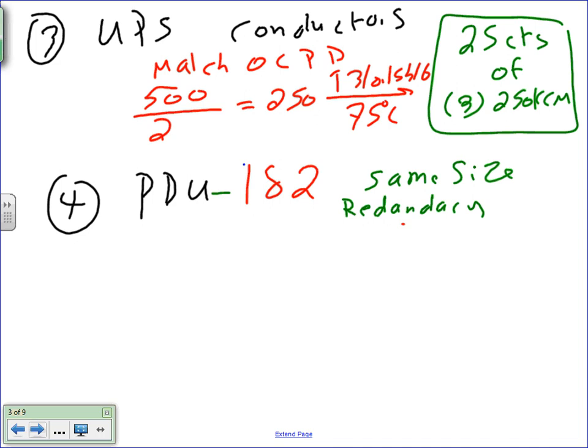Okay, now PDU 1 and 2. I said same size, guys, as the UPS. The same way we size it. I'm not going to repeat the steps. Same way like the UPS, so you're going to get the same calculation, same sizing. Everything is the same, and we have two of them for redundancy. So we're going to size them 100%. Both of them are going to be the same size for redundancy. Remember how if one of them fails, you shift the load to the other one.